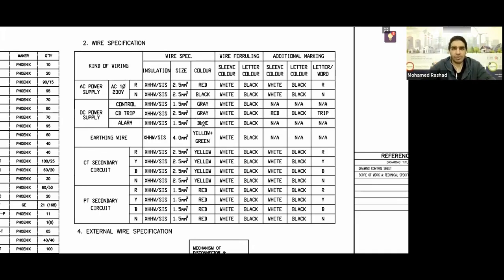All the AC circuits, you will find their size is 2.5 millimeters, while the control circuits are all 1.5 millimeters, and the alarm is 1.5 millimeters. The circuit breaker tripping is 2.5 millimeters.